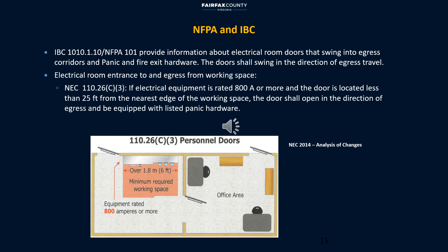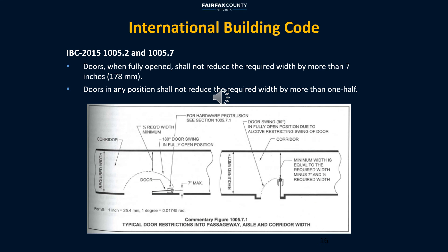As you can see in this figure, there is no 25-foot space between equipment and each door. Also, the electrical room is right next to an office area, which is not considered egress. Therefore, panic hardware shall be provided with each door leading to egress. Doors opening into the egress shall not block the passageway. IBC provides some rules to calculate where doors need to be installed with respect to the width of the corridor without compromising fire and building code requirements when doors are open at 90 or 180 degrees.